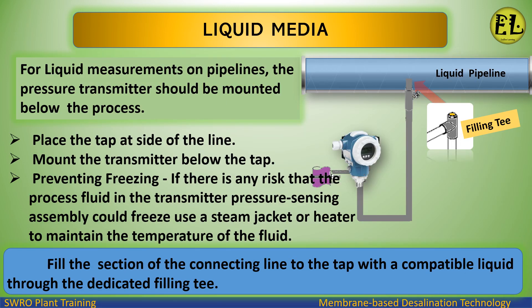Liquid Media: For liquid measurements on pipelines, the pressure transmitter should be mounted below the process. Place the tap at the side of the line and mount the transmitter below the tap. If there is any risk that the process fluid in the transmitter pressure sensing assembly could freeze, use a steam jacket or heater to maintain the temperature of the fluid. Fill the section of the connecting line to the tap with a compatible liquid through the dedicated filling tee.